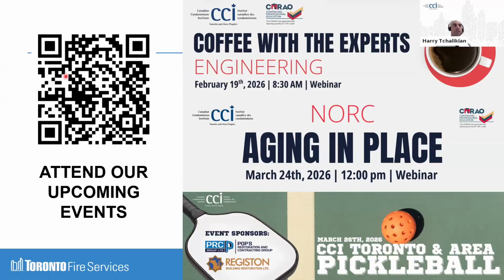I'd be okay with confirmation, because it's not the same as a fire alarm test that has to be done by a CFA technician. You need to account for that fact, but there is due diligence involved with all of this stuff. Make sure you do your due diligence. If you're only putting that responsibility on others, that may not qualify if ever something comes up. You may still want to be doing a hands-on sampling yourself as well as delegating. And also, don't forget, I'm not a lawyer, so I don't actually know how this would play out if something bad happened. So the answer to that question is due diligence. But I would accept that personally as an inspector if you had confirmation, some kind of record that it was addressed.